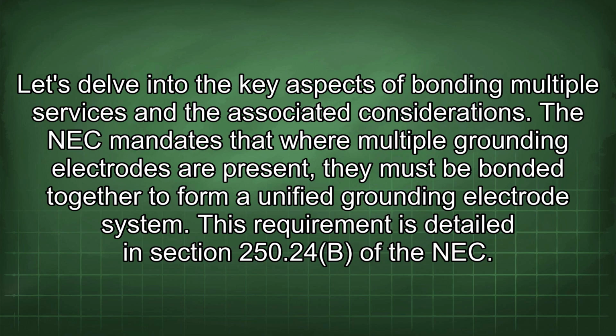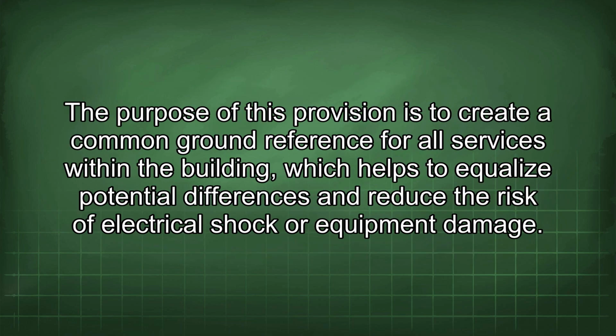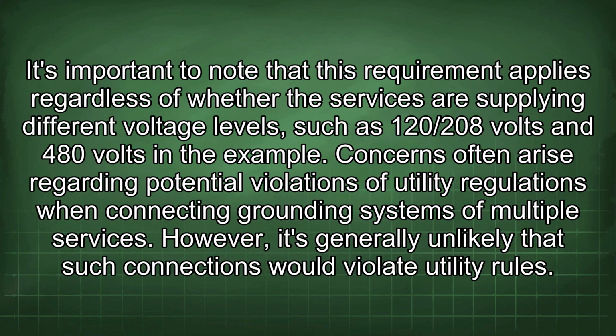The NEC mandates that where multiple grounding electrodes are present, they must be bonded together to form a unified grounding electrode system. This requirement is detailed in Section 250.24(B) of the NEC. The purpose of this provision is to create a common ground reference for all services within the building, which helps to equalize potential differences and reduce the risk of electrical shock or equipment damage. It's important to note that this requirement applies regardless of whether the services are supplying different voltage levels, such as 120/208 volts and 480 volts in the example.